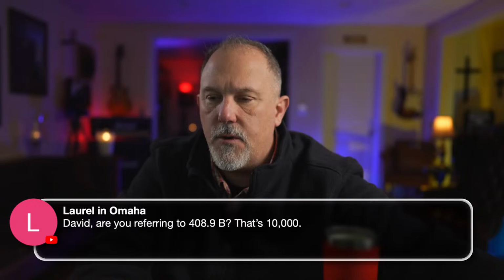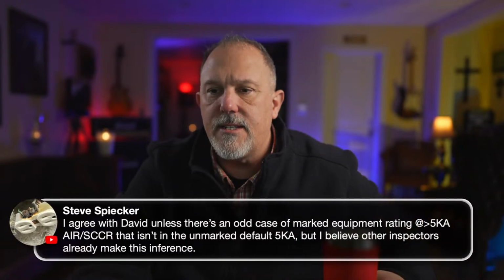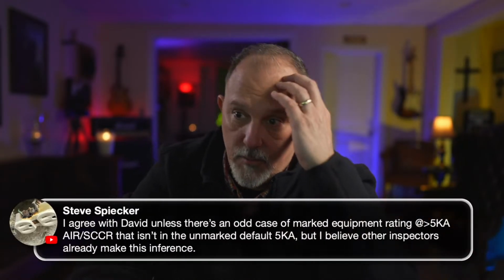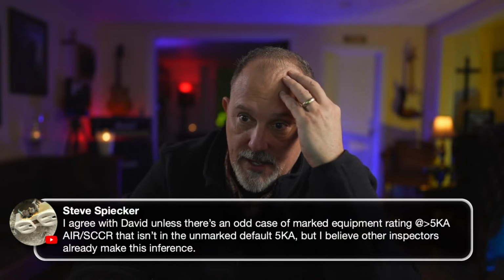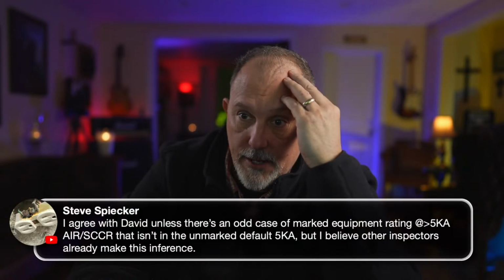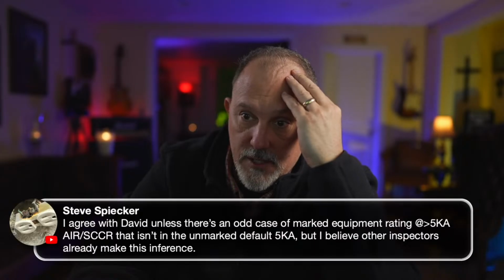How do I do this? All right. Laurel said, David, you're referring to 408.9b. That's 10,000 amps. And then Steve says, I agree with David, unless there's an odd case of marked equipment rating greater than 5KA AIR, that isn't the unmarked. I believe other inspectors already make this reference. And then there's the 240.83, Charlie. And we added a new 240.16. Woo! I love it.